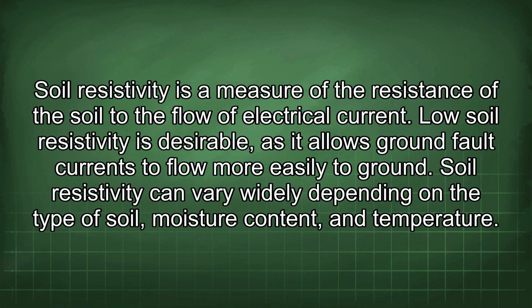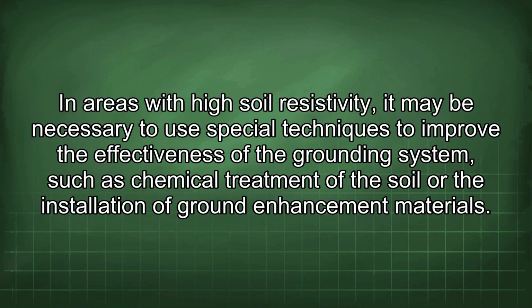Soil resistivity is a measure of the resistance of the soil to the flow of electrical current. Low soil resistivity is desirable, as it allows ground fault currents to flow more easily to ground. Soil resistivity can vary widely depending on the type of soil, moisture content, and temperature. In areas with high soil resistivity, it may be necessary to use special techniques to improve the effectiveness of the grounding system, such as chemical treatment of the soil or the installation of ground enhancement materials.